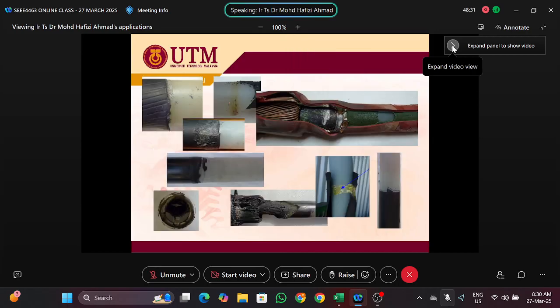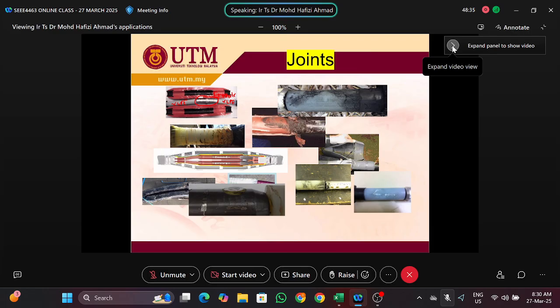Okay, so this is like a conductor to join between two cables, right? And then you might see here, so this is called a deflector, or they call it a stress cone. So this is semiconductor material, used basically for cable entry fitting. So this is used to linearize the electric fields. This is called geometric field grading. It grades the electric fields so that the electric field will not concentrate at one point, it will be linear away from the stress point or away from the cable entry fitting.